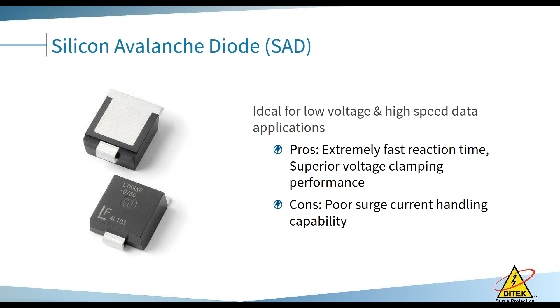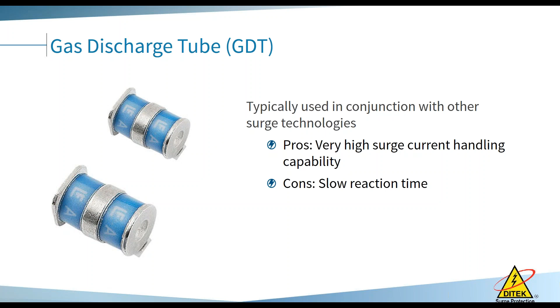So if we only had a single stage in there, we'd be popping these devices all the time. So what we do is we use those steering diodes in tandem with a gas discharge tube, which has a really high surge current. So we steer it into this device, which has a 20,000 amp rating. This has a slower reaction time if it were by itself, but in tandem with the silicon avalanche diode, it is quick and responsive, with very low capacitance on the circuit, because we're going to get asked a lot, if we haven't seen it in the chat already: can you put these on a 100-meter circuit? They're almost invisible. The dB loss is very little.